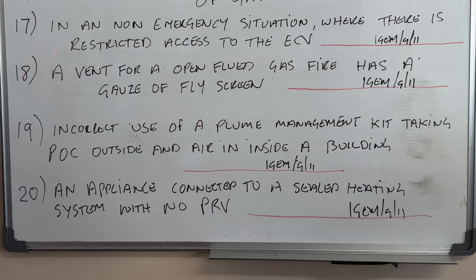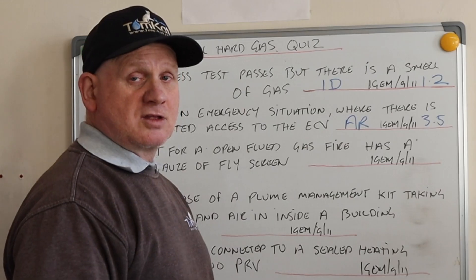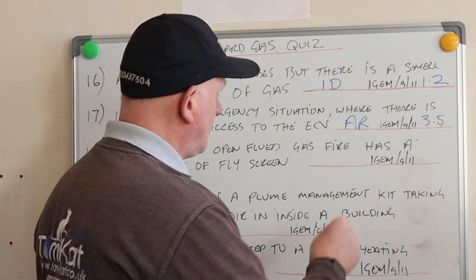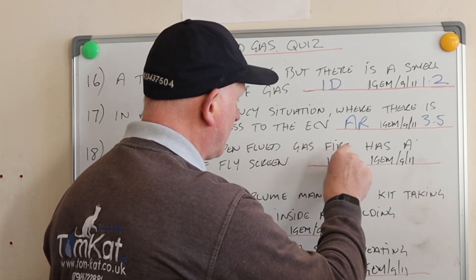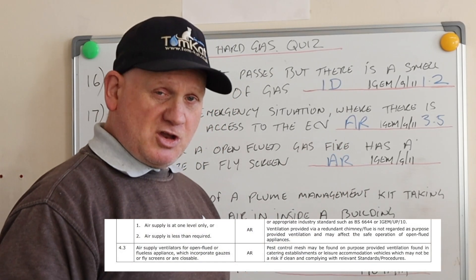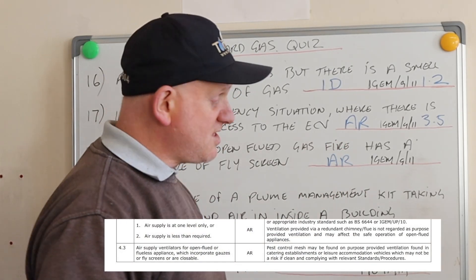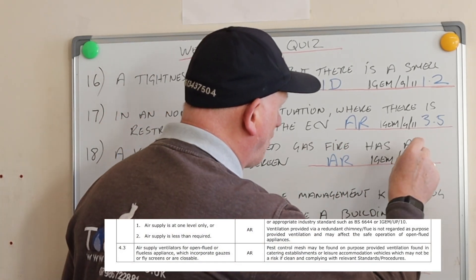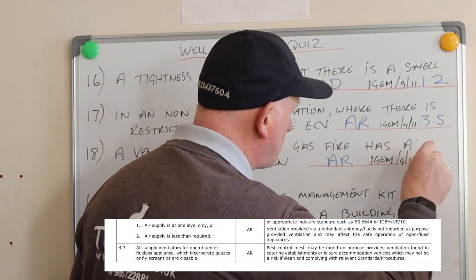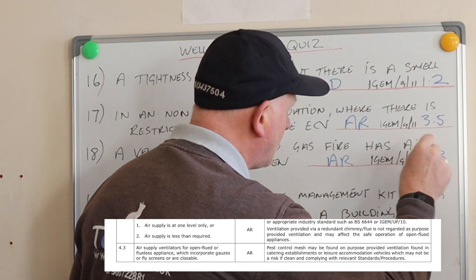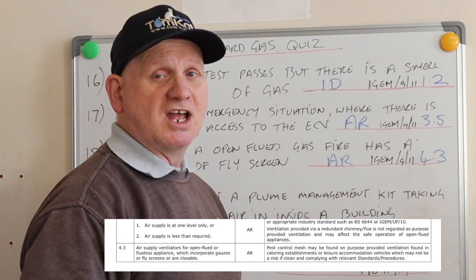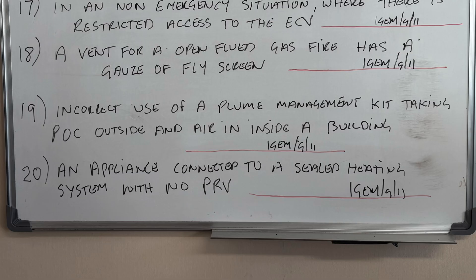Question eighteen: a vent for an open flued gas fire has a gauze or a fly screen. Hopefully you said it's 'at risk,' and if you want to know where it is, it's at section 4.3 of the IGEM G11.